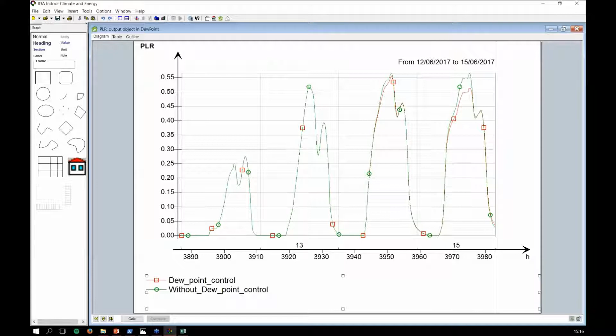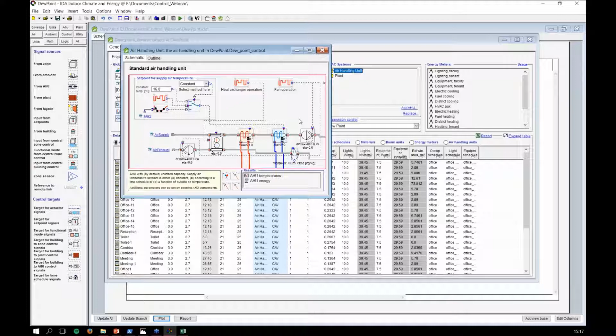So one issue arises from this dew point control, and I think you pointed this out to me the other day, is IDA ICE models the system's physics very realistically. So basically, when the air handling unit is off and you have a humidity sensor on the return, that humidity sensor is going to give wrong signals. It's going to go berserk, basically. And the same thing happens in IDA ICE. In IDA ICE, when you turn off the ventilation signals, numerically we turn down the mass flow to a very small number, an epsilon, 10 to the minus 12. And then when that mass flow rate is 10 to the minus 12, that humidity ratio will go nuts on you and give you false readings.